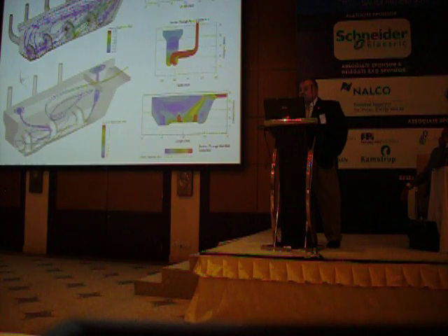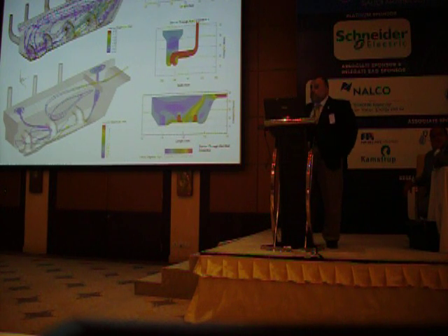And if you see here, this is the length and the cross section, and it will also give you the velocity magnitudes surrounding the pump, which cannot exceed, for example, 2 meters per second. This is also a T-junction. A very simple T-junction, you can also simulate the flow within the T-junction. Also, if you use an RO system, you have a pressure vessel and a membrane, spiral wound, already installed within the pressure vessel.